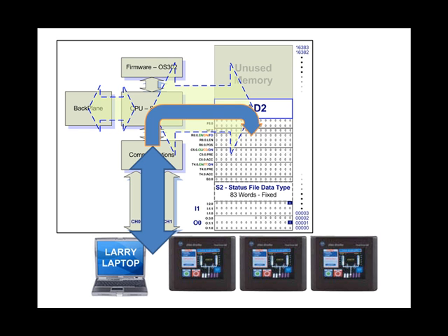In this industry, we refer to this type of system as having naked data. That means that while you are intently troubleshooting this machine, a board operator can be walking by, poking buttons at random, and changing the data in the data table. Even changing the screen on an MMI can change a variable in the PLC. And of course, Larry Laptop, which should be you, can change any of the variables directly from the keyboard.